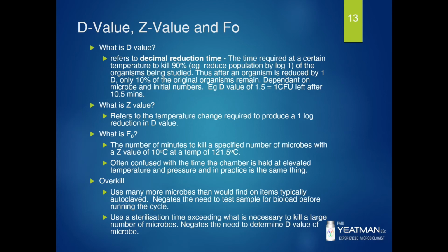Z value refers to the temperature change required to produce a 1 log reduction in D value. And then we have this thing called F0, which is the number of minutes to kill a specified number of microbes with a Z value of 10 degrees C at a temperature of 121.5 degrees C. That's often confused with the time the autoclave is held at elevated temperature and pressure, and in practice it's the same thing anyway. And what is this thing called overkill that I've mentioned a few times?